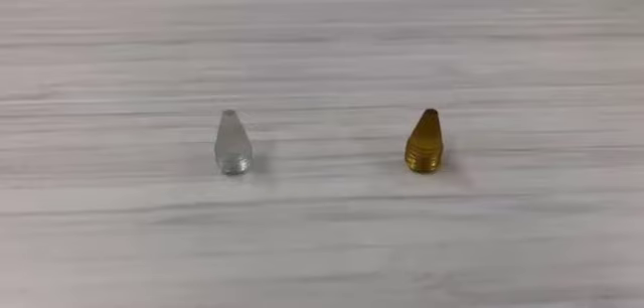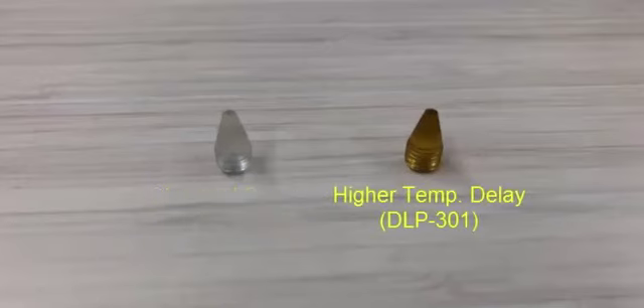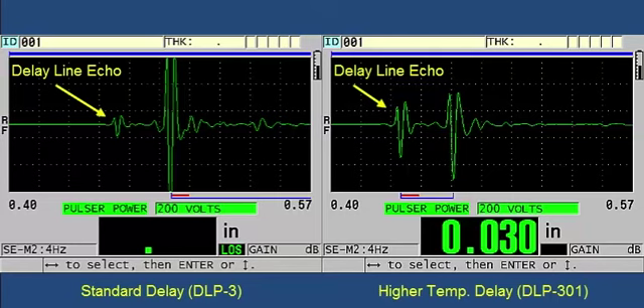For this demo, we showed how to make the plastic measurement using the standard Sonopen delay tip. As discussed in previous slides, using the higher temperature DLP-301 delay tip may be a better choice when measuring some plastics, since it can help create a stronger delay line echo by offering a greater acoustic impedance mismatch. As you can see from the images shown, when using the same transducer setups, the screenshot that utilizes the higher temperature DLP-301 delay tip creates a stronger delay line echo, and the gauge is already making detection. Therefore, if you are having trouble detecting the delay line echo when using the standard delay line tip, you should try using the higher temperature DLP-301 delay tip.